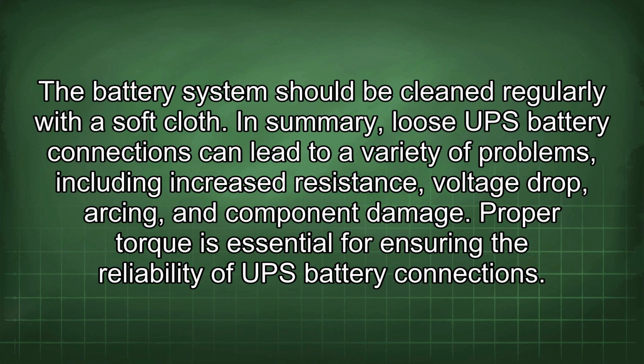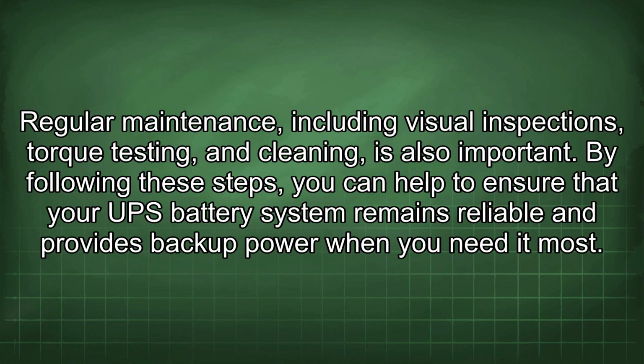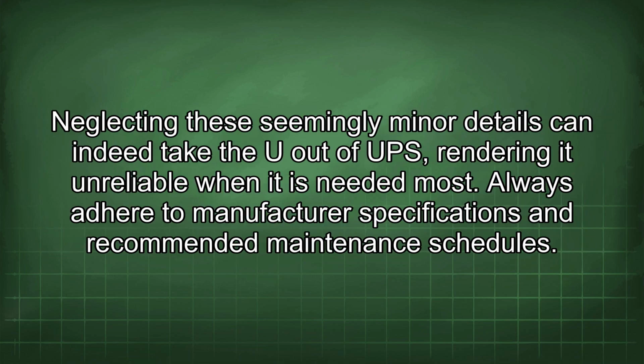In summary, loose UPS battery connections can lead to a variety of problems, including increased resistance, voltage drop, arcing, and component damage. Proper torque is essential for ensuring the reliability of UPS battery connections. Regular maintenance, including visual inspections, torque testing, and cleaning, is also important. By following these steps, you can help to ensure that your UPS battery system remains reliable and provides backup power when you need it most. Neglecting these seemingly minor details can indeed take the U out of UPS, rendering it unreliable when it is needed most. Always adhere to manufacturer specifications and recommended maintenance schedules.